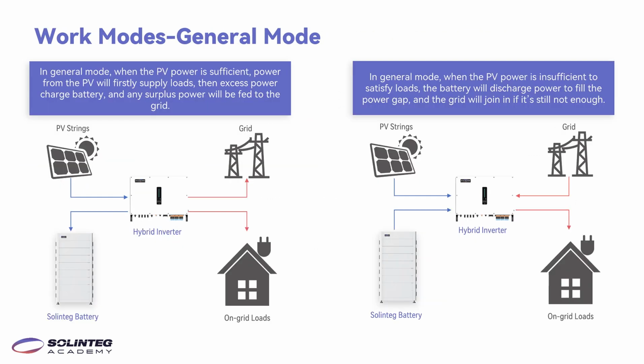Okay, I think we have come to the last part, the work modes. So let's introduce them one by one. The first work mode is general mode. In the general mode, the PV power is sufficient. The power from PV will first supply the load, then excess power will charge the battery, and any surplus power will be fed to the grid. When the PV power is insufficient to supply the load, the battery will discharge power to fill the power gap, and the grid will join in if it is still not enough.